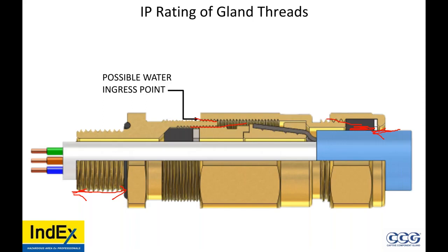It's not simplistic for the installer. If the manufacturer does not make their gland simplistic, they're being lazy and putting the onus on the installers. 80% of all non-conformances, yeah, punch listing within our industry is glanding and terminations. If the gland is difficult to use or is claimed to never cause cold flow, did they test on every single cable type in the world? That is not possible. A simplistic device ensures safety.